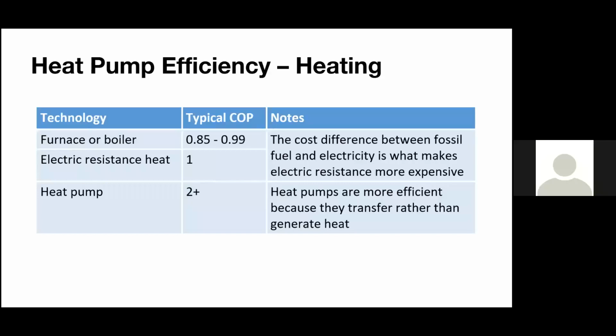And then we look at heat pump systems, which is a lot different than electric resistance heat. We are still using electricity. However, instead of using that power to generate heat, we're using the power to transfer the heat, as Adam's mentioned in his previous slides. So we're taking that heat out of the ambient air and bringing it into a different space. And heat pump systems at lower temperatures can be 2+, and at mild temperatures maybe even 3 or 4. So it's a lot more efficient that way, and it's just a solution to look at.